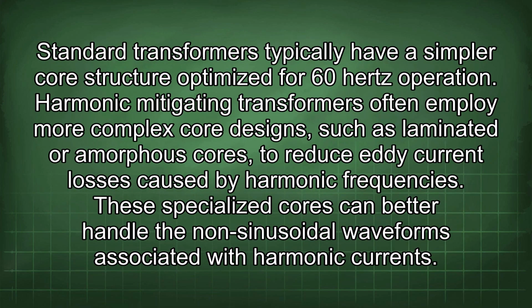These design modifications enable the transformer to handle harmonic currents more effectively, reducing overheating and improving overall system performance. Standard transformers typically have a simpler core structure optimized for 60 Hz operation. Harmonic mitigating transformers often employ more complex core designs, such as laminated or amorphous cores, to reduce eddy current losses caused by harmonic frequencies. These specialized cores can better handle the non-sinusoidal waveforms associated with harmonic currents.